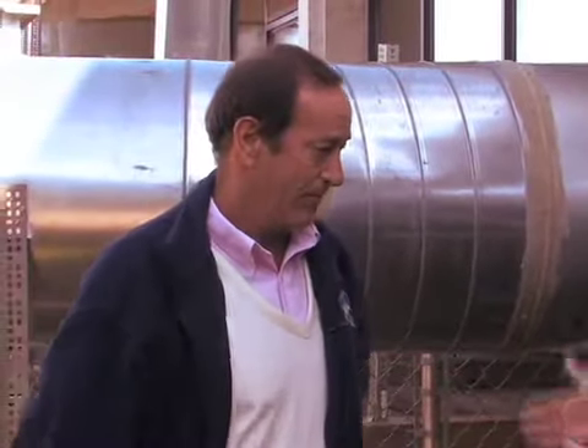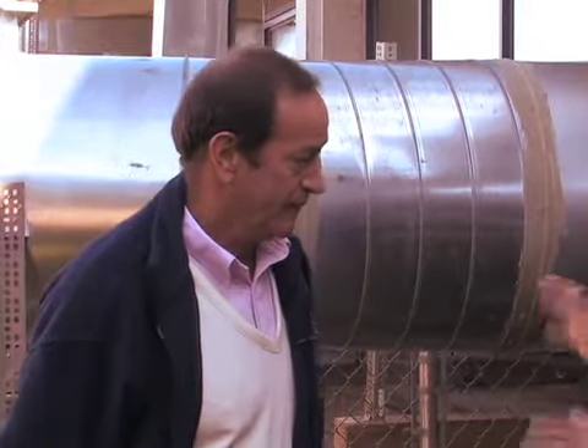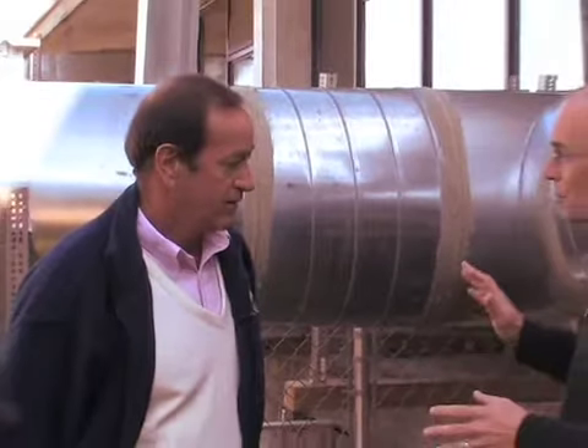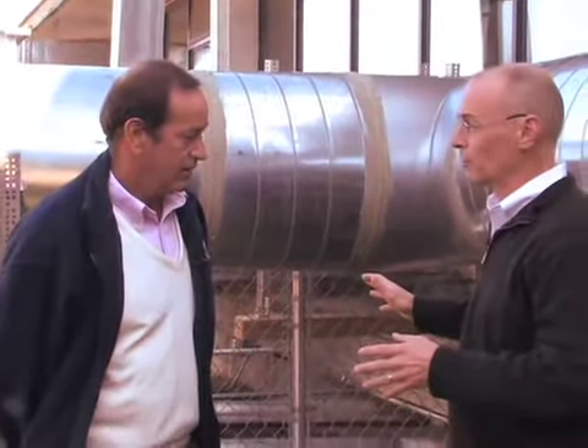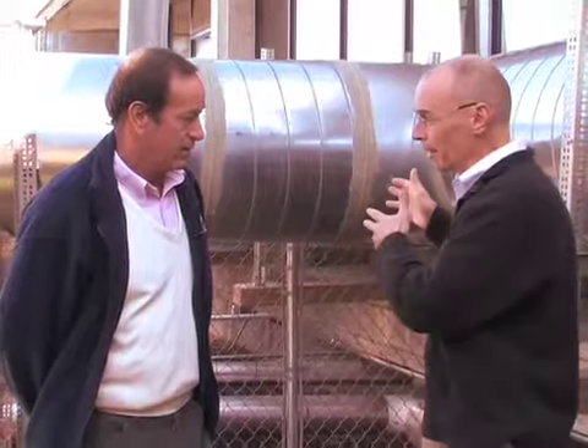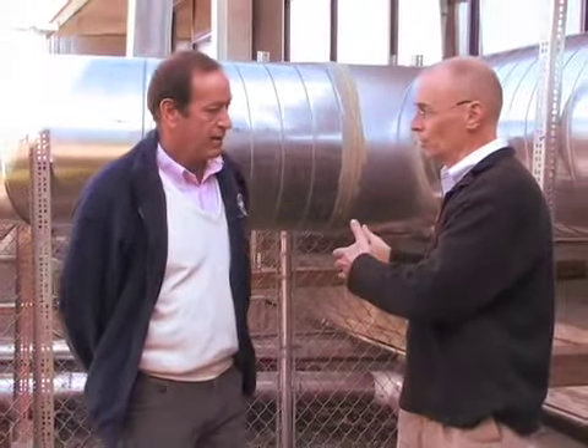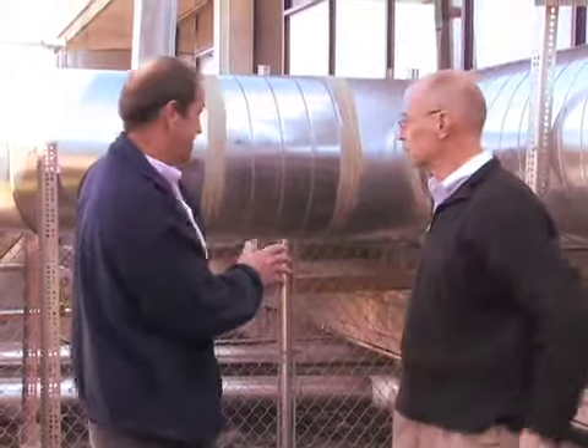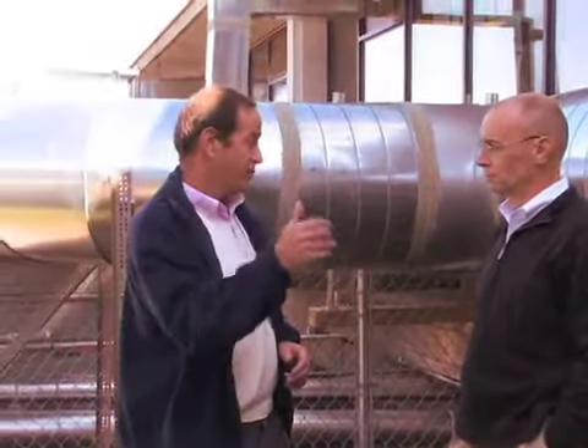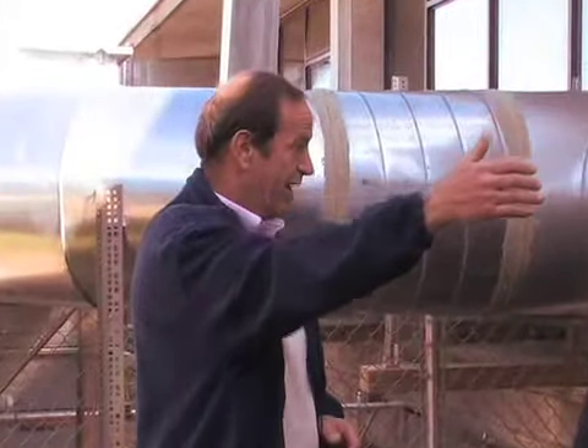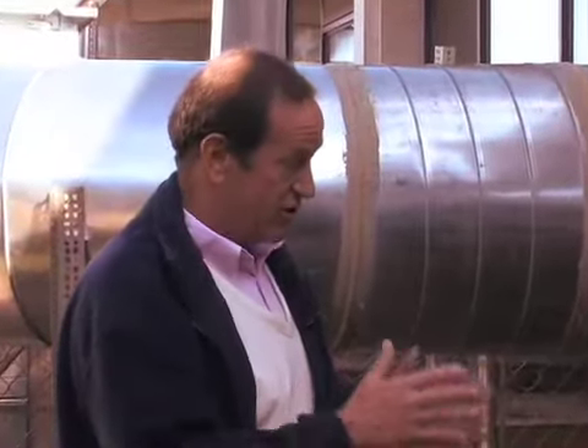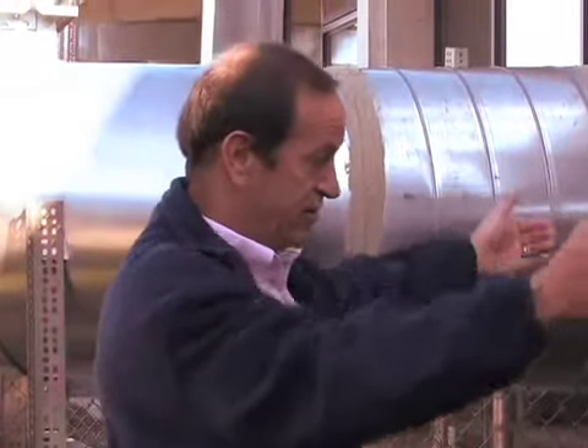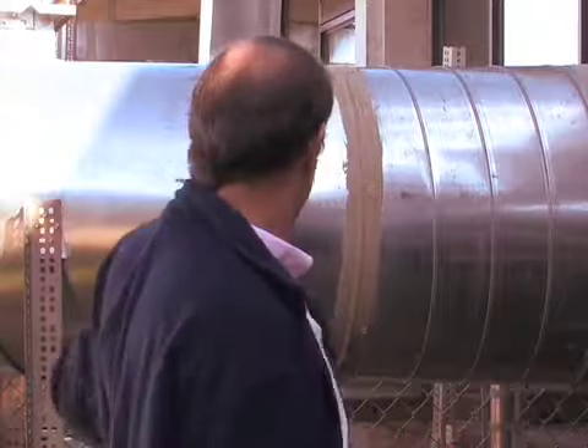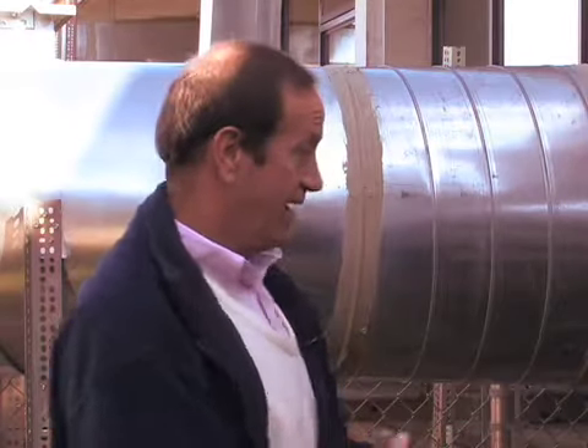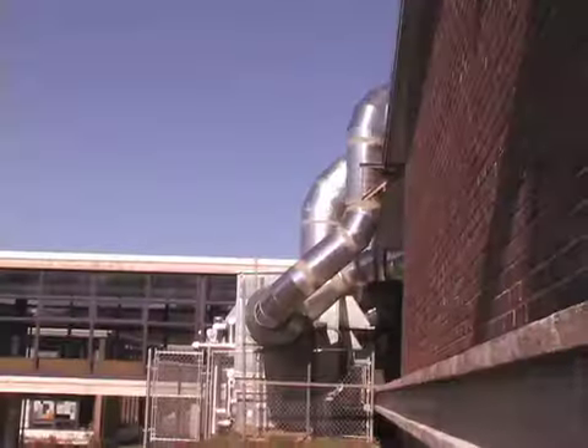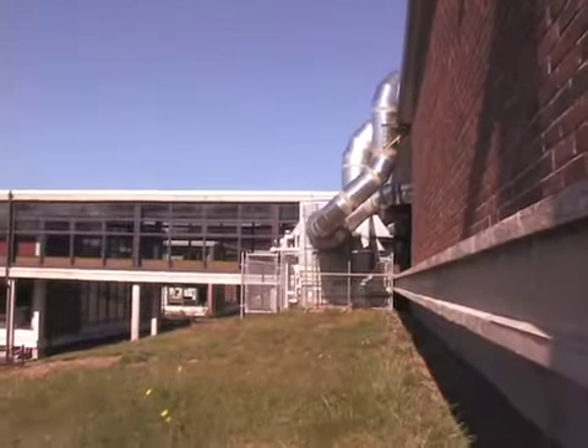And by the way, you need to have some ongoing maintenance to make sure that, as you said, everything's working. So this is a different kind of maintenance problem than you would have in one of our newer buildings, where there'd be less hands-on maintenance keeping the system running throughout the winter. That's correct. Because of the way the system is set up, we have to constantly check the programming in the old air handling room as the seasons change and change the programming to adapt it to what's needed inside the classrooms. Additionally, the control valves have to be inspected almost on a weekly basis to make sure they're doing what they're supposed to do. All right, thank you.